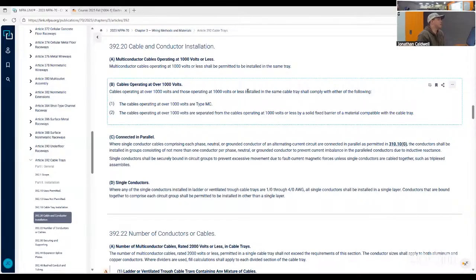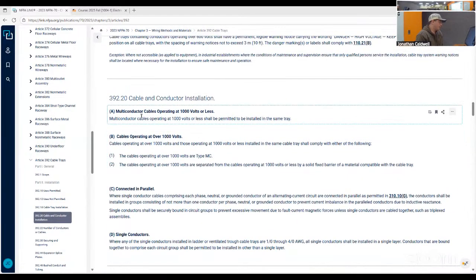Or no. Yes. Even though it says you can have combined voltages, the insulating jacketing for those cables has to be rated at 1,000 volts. So even though, say I got, I don't know, 600 volts in this cable, 480 volts in this cable, and just say 208 and 120 in the rest, every single one of those outside insulating jacketing for that cable has to be rated at 1,000 volts. Doesn't matter what kind of voltage is going through it. Otherwise, you'll have some weird voltage leaking.